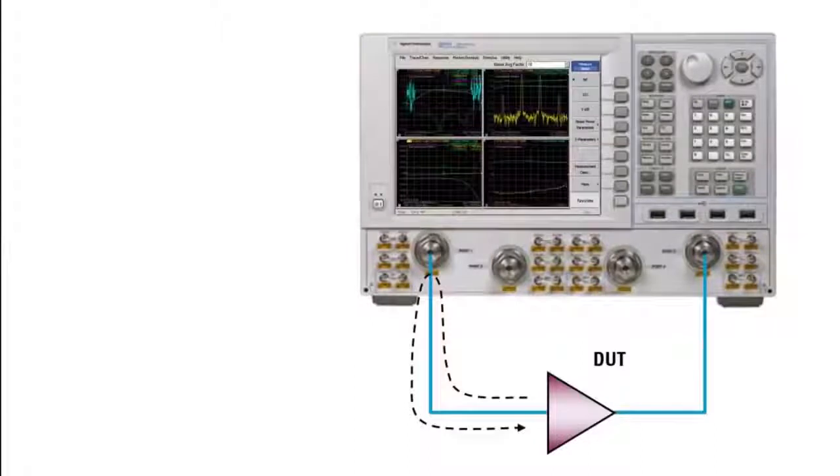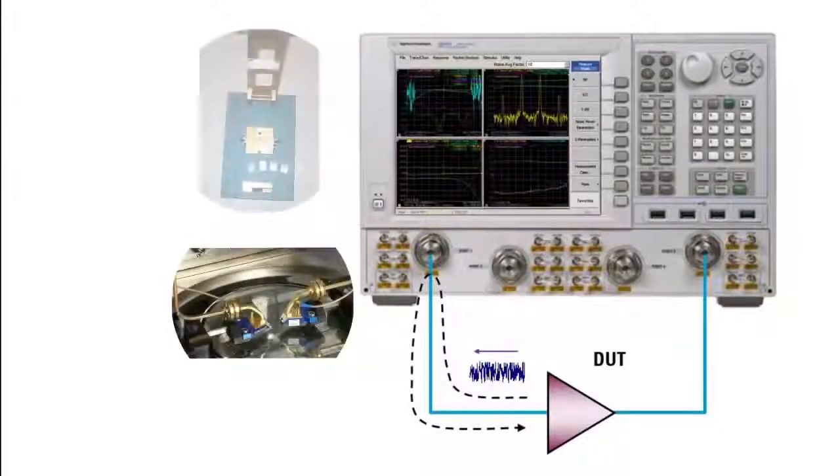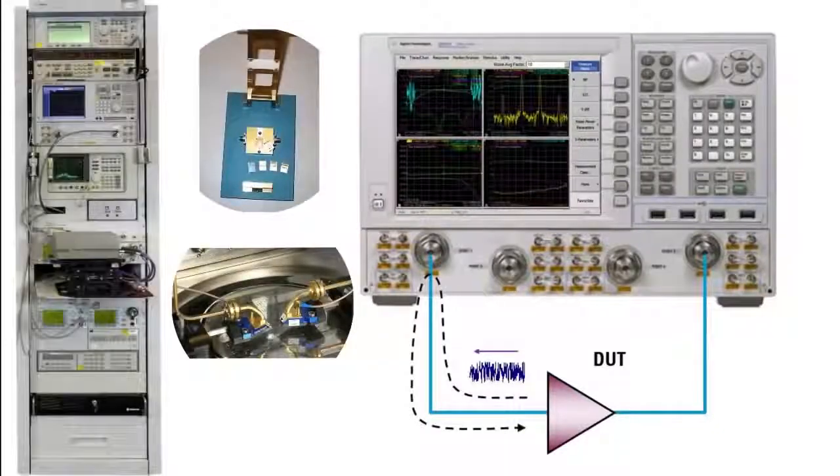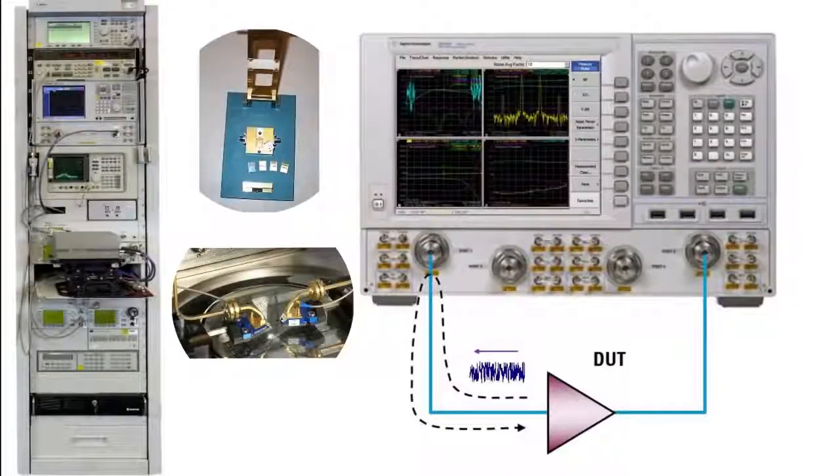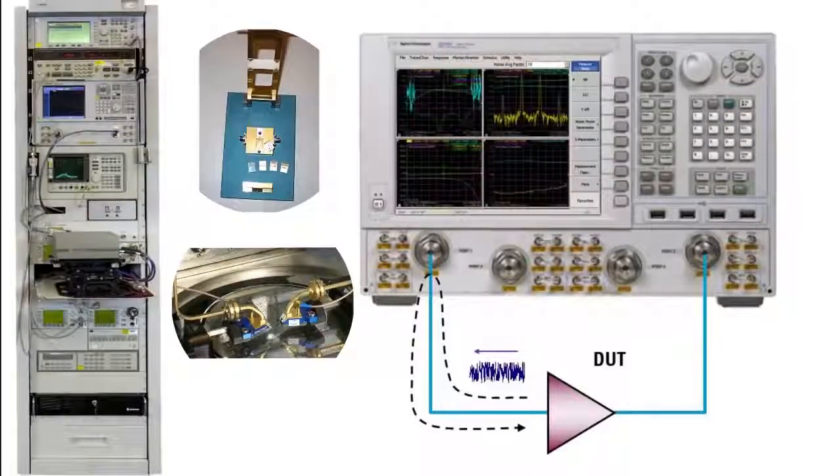Another major source of error comes from the noise coming out of the DUT's input and interacting with the non-50 ohm source match. This is especially troublesome in on-wafer, in-fixture, or automated test environments where the system source match is degraded by the additional hardware required to connect the analyzer to the DUT.